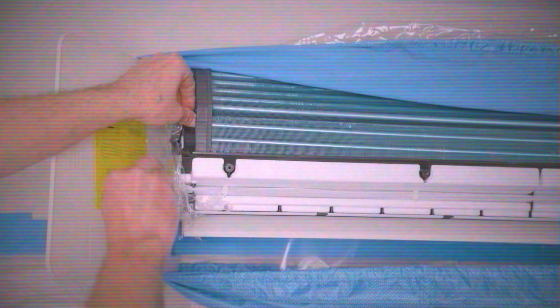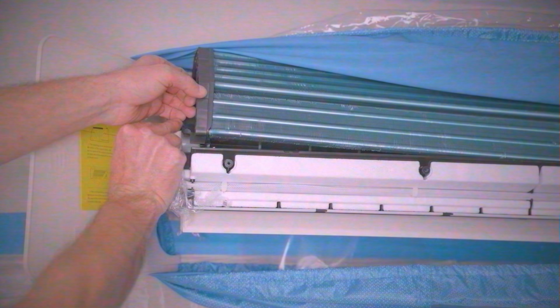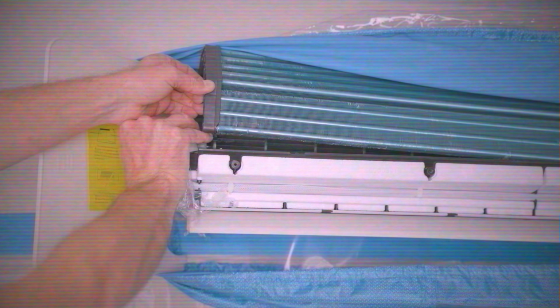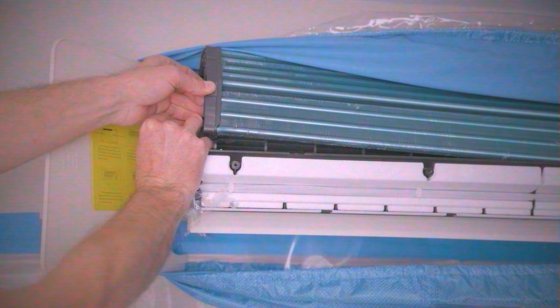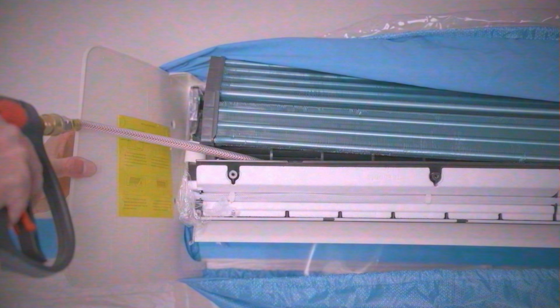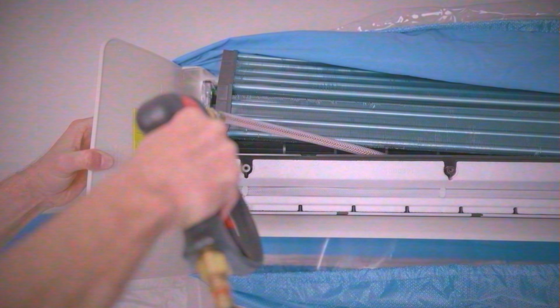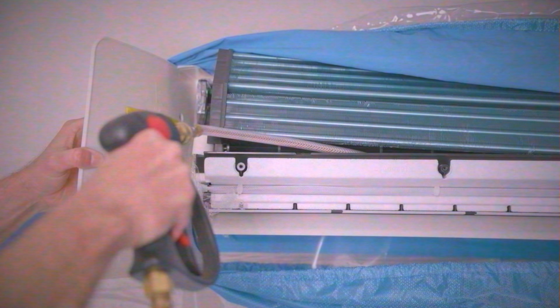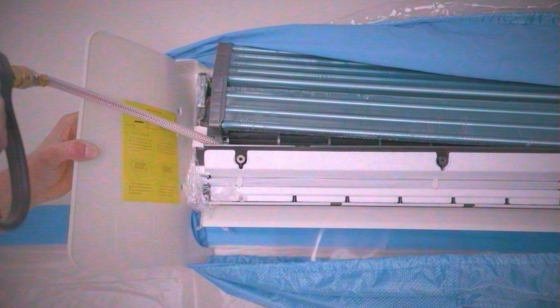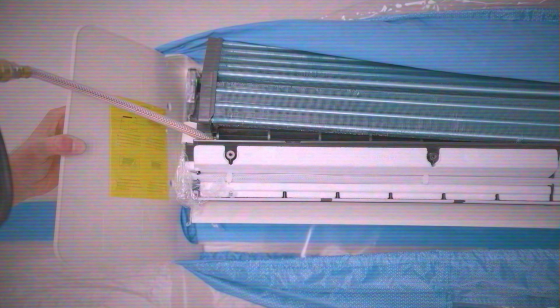Now let's clean the drain pans. If needed, gently lift the left side of the heat exchanger, no more than 2 inches to avoid damaging the refrigerant pipes. Spray into both the front and rear drain pans. Debris often settles here, so be thorough and pay special attention to the drain outlet to prevent clogs during rinsing.